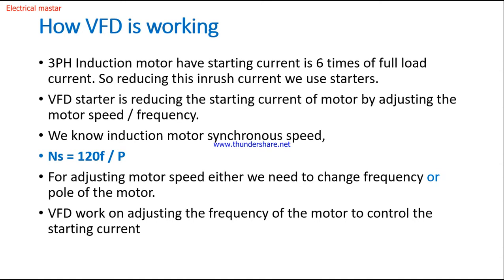How does VFD control the speed of the motor? The speed relation of the induction motor is Ns = 120f/P, meaning synchronous speed is directly proportional to frequency and inversely proportional to the number of poles. To control the speed, we can increase or decrease the frequency or the number of poles. Increasing poles is very difficult, so we choose VFD to easily adjust the frequency and control the motor speed.